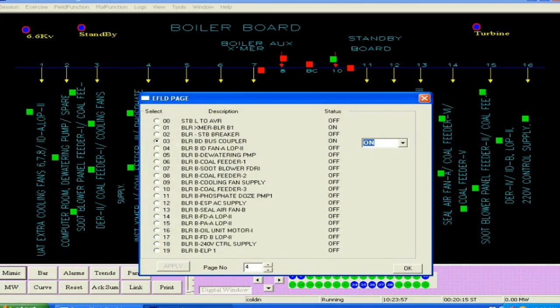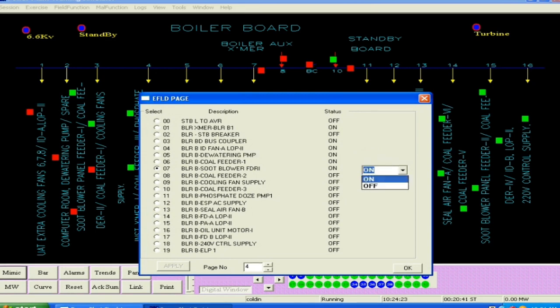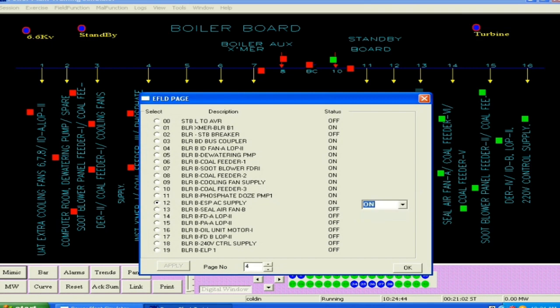So once these breakers are on, the supply will be extended to the auxiliaries through the boiler board. You can see the board has been charged when we have made the supply on. Here we have a bus coupler in between. There are two sections of the boiler board, and there is a bus coupler between the two sections. The bus coupler has been made on so that the supply from the boiler auxiliary transformer goes to both sections of the board. So all the supplies have been made on so that the breakers can be operated from remote. The supplies are extended to all the auxiliaries.